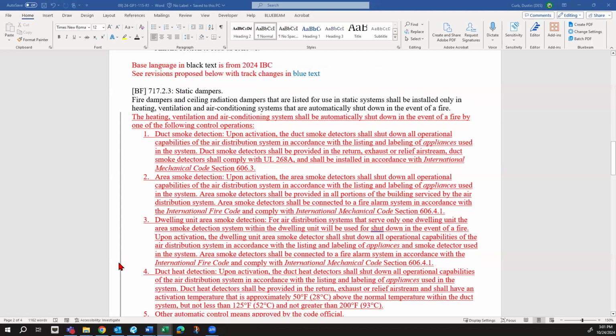As for the technical pieces here, I like having this additional option. As Eric mentioned, take a 400 unit apartment building - they still always have the option of that soffit-down direct exit, which doesn't penetrate a fire resistive assembly, so in those cases they wouldn't require the fire dampers or radiation dampers anyway. From a cost aspect, they still always have those options. The only time you need the dampers is when you're actually penetrating that fire resistive assembly, and all the more reason we want it to be as protected as possible. So yes, I'm in support of this.